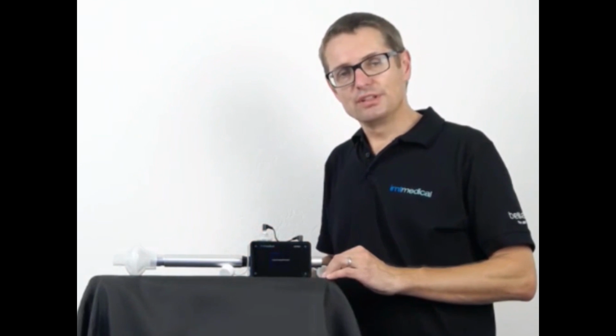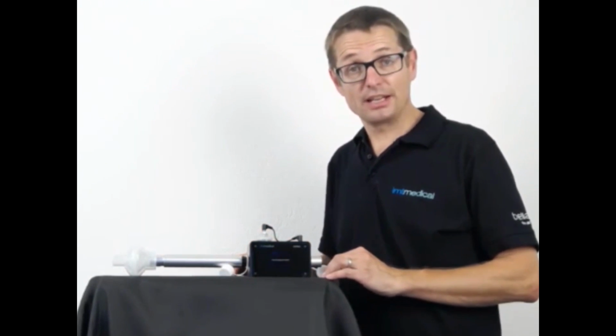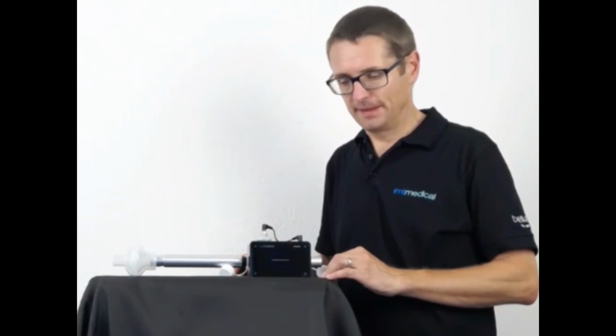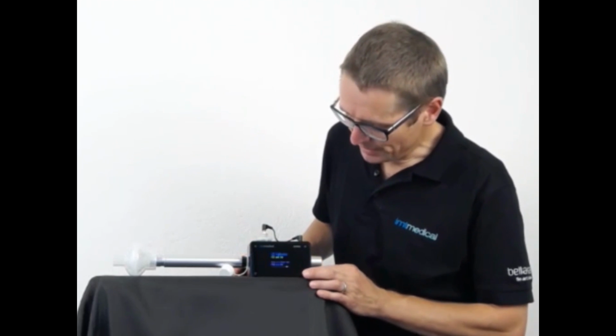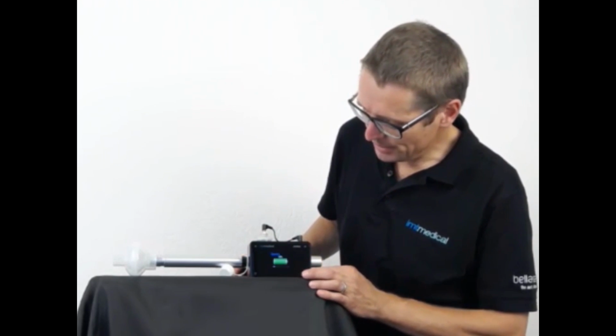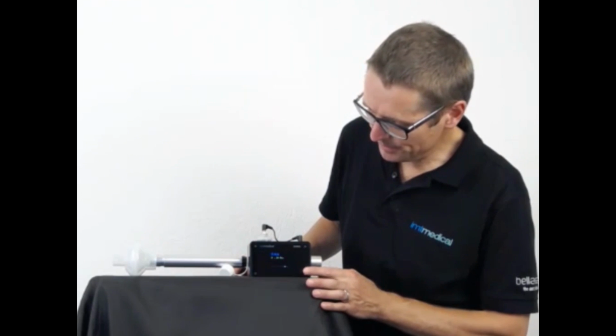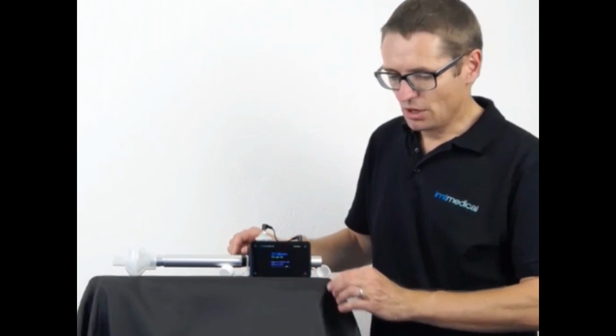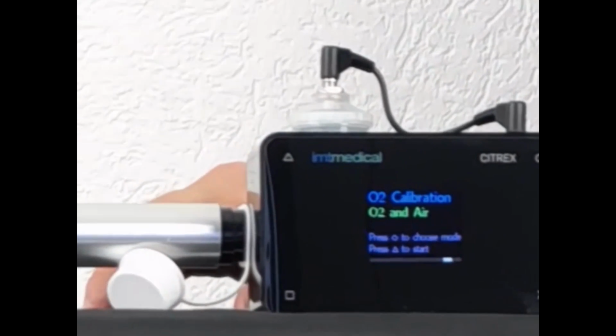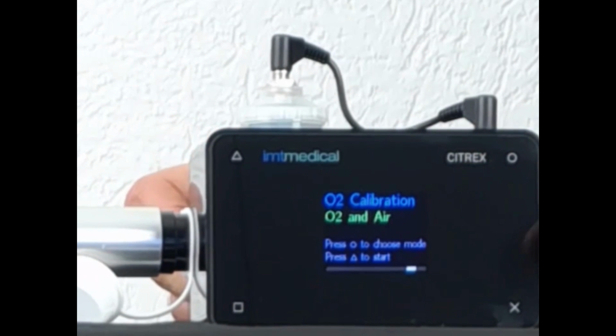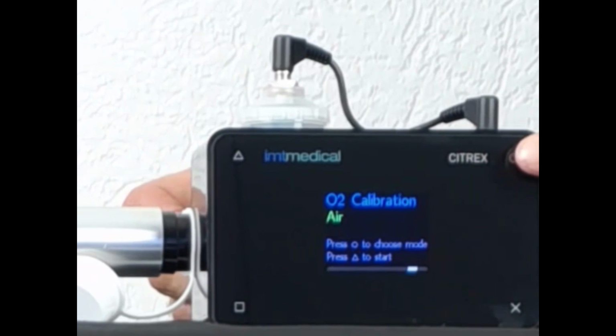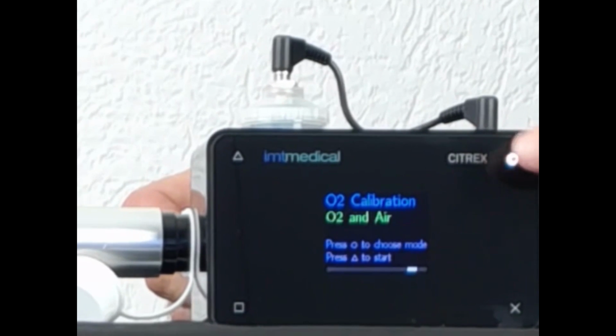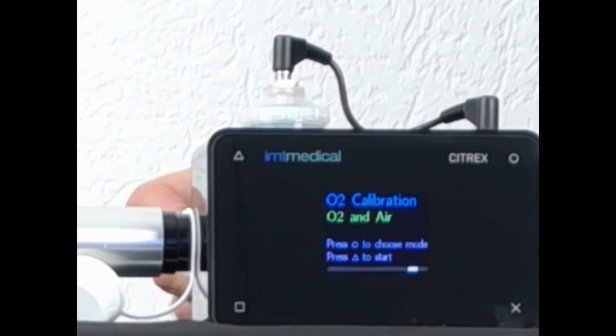Now let's do the oxygen sensor calibration. Again, the oxygen sensor calibration only has to be performed once a week. I go to the service menu, go to oxygen calibration. By clicking several times, oxygen sensor calibration, there is an oxygen and air calibration. Let's have a look at the display in more detail. So there is the possibility to perform an oxygen and air calibration, or alternatively an air calibration only. Air calibration is easier, faster, and in most cases sufficient. For completeness, we will perform an oxygen and air calibration.